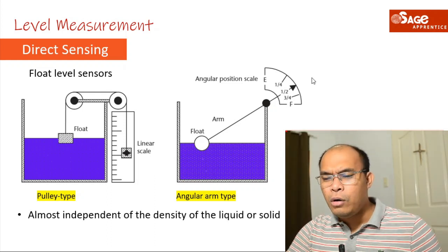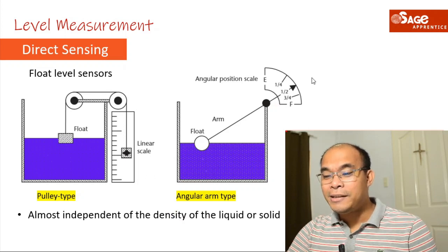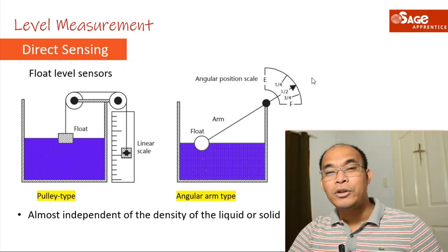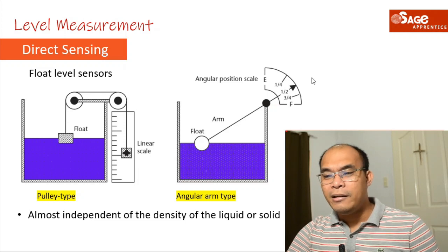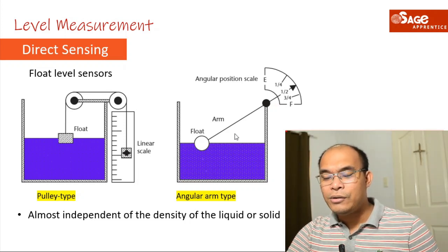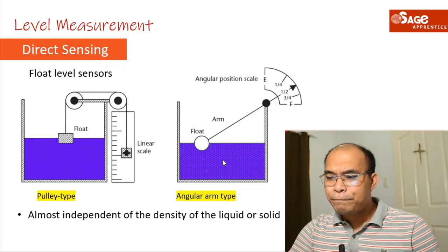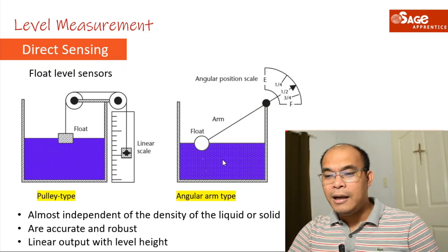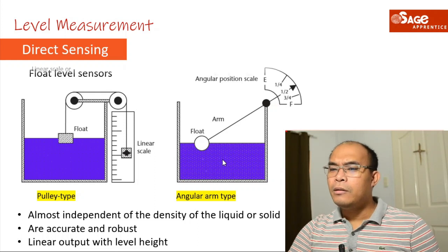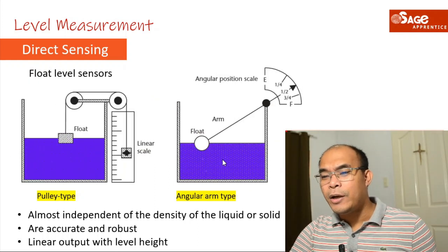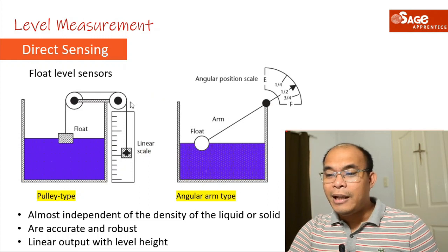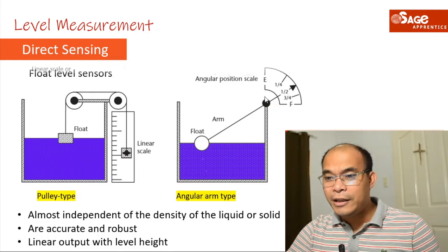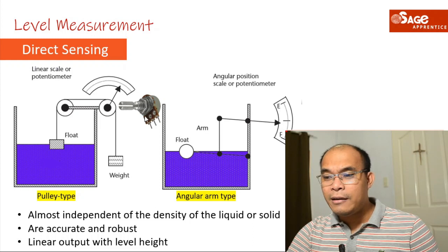Float level sensors are almost independent of the density of the liquid or solid — density being mass over volume — so it doesn't matter what the liquid is. They are accurate, robust, and produce a linear output with level height. We can also replace the mechanical indicator with a potentiometer.